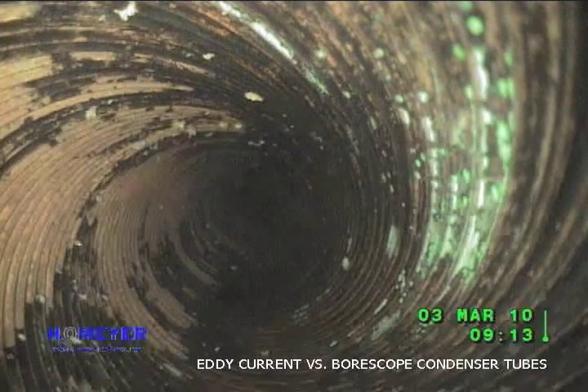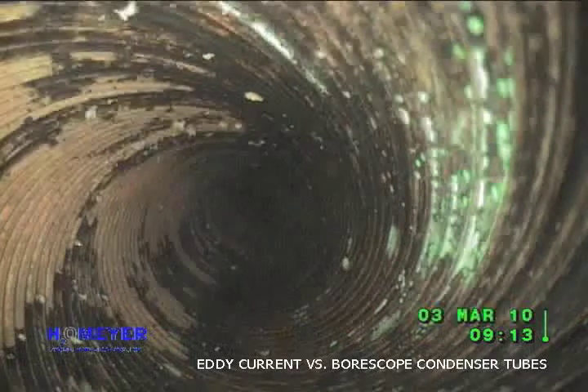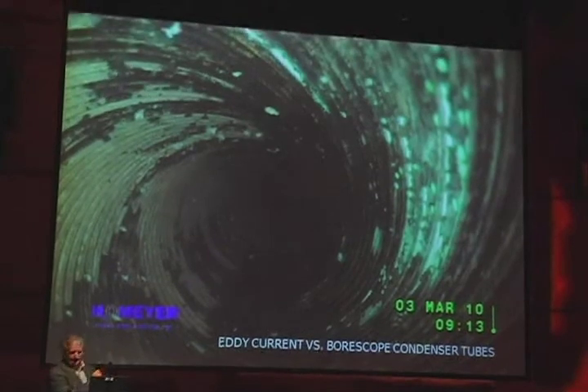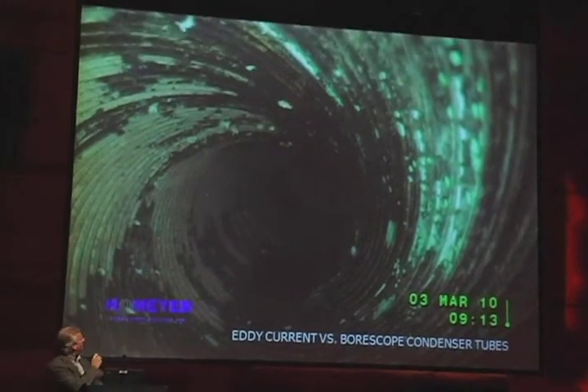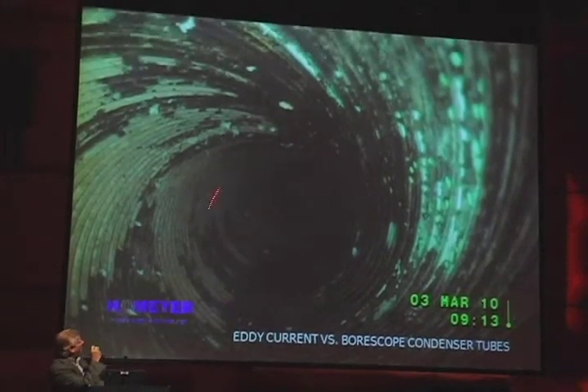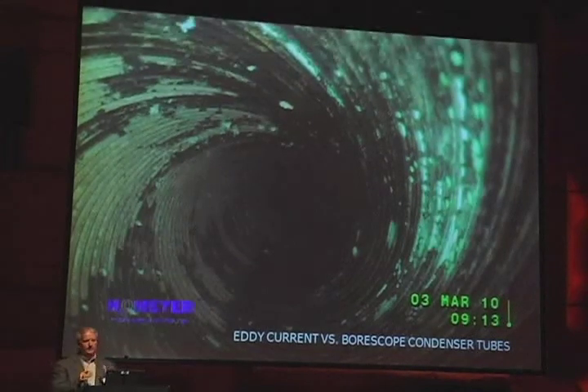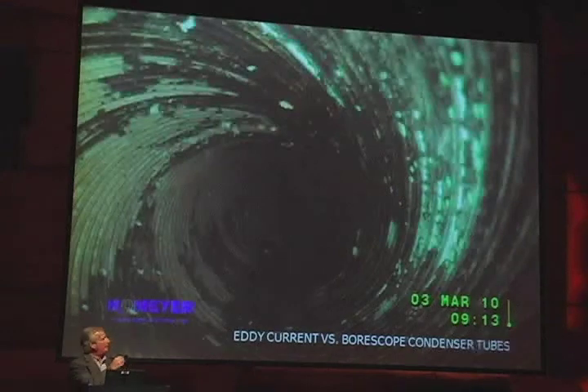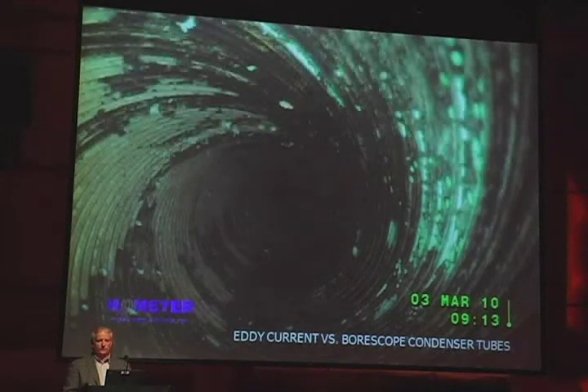One of the things you want to do is look inside the tubes. If you have condenser tubes, most of the tubes now are what they call enhanced tubes. They're enhanced not only on the outside on the freon side, but also on the inside. It's basically a rifle barrel that goes through there. I don't know if you guys can see that very well. Can you see that very well? Basically, it's a rifling that goes through the tubes, and the purpose is to increase the surface area of the tube. By rifling it, you've got the valleys and grooves and everything else, so you actually increase the surface area of the tube, allowing better heat transfer surface.